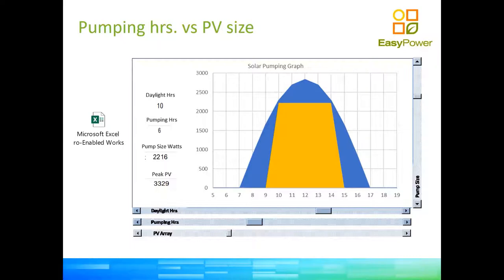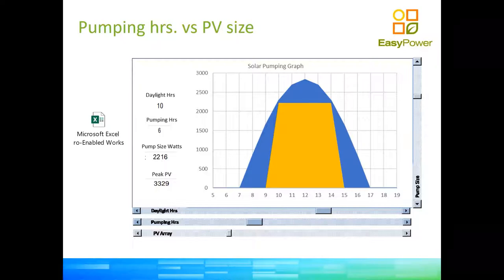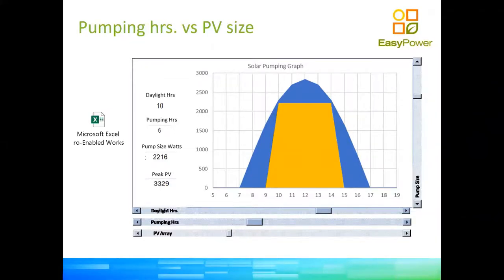At 50 hertz, the pump runs at 2,550 RPM — whatever RPM your motor is designed to run at that frequency — at 100% power. To the left of that flat section, from about 9 in the morning, the pump starts running slowly. If it is a submersible pump you might not even see water, because the pump is just pushing water up the column until it develops enough energy to push water to the surface. If it is a centrifugal surface pump, you'll see a trickle of water quite immediately if there is no back pressure on the outlet.